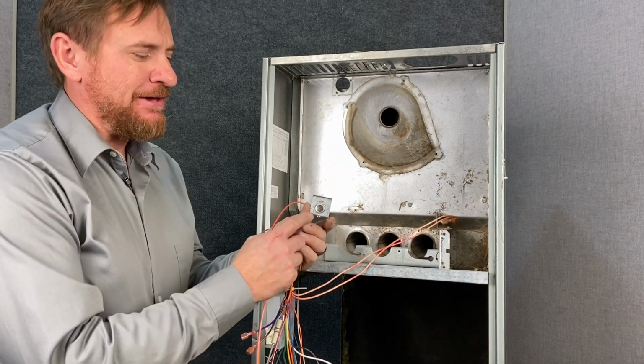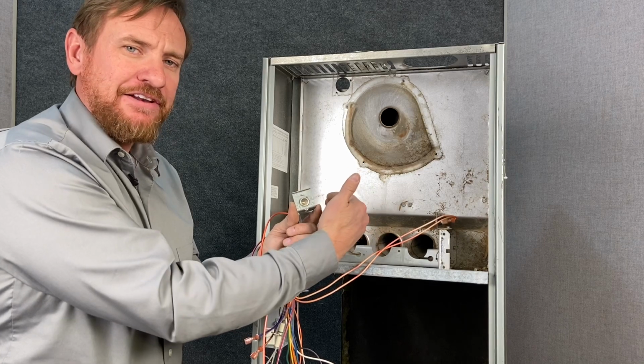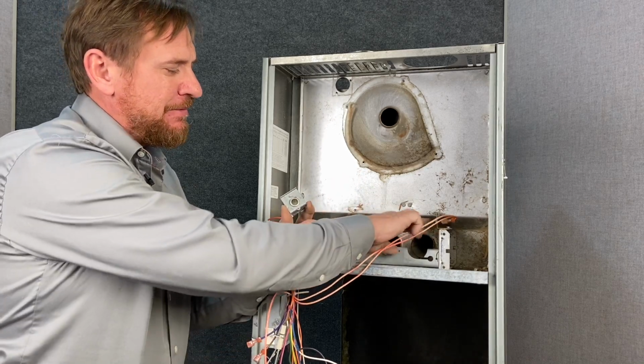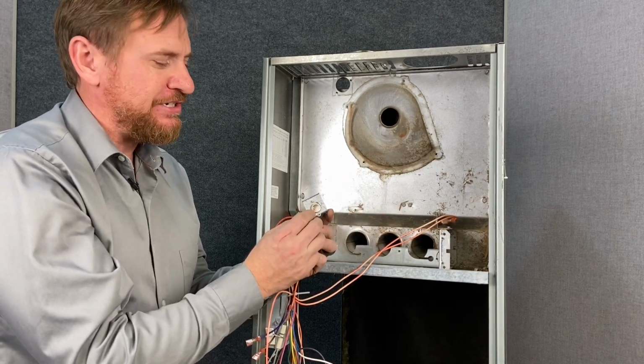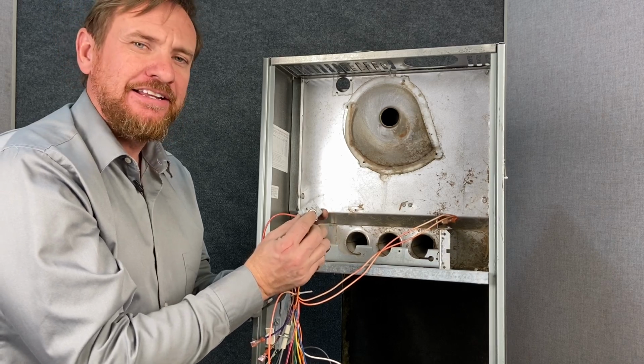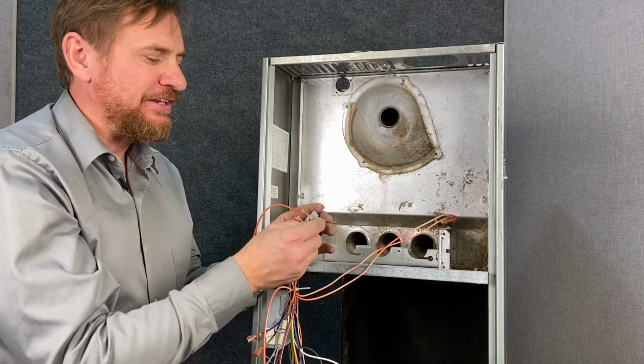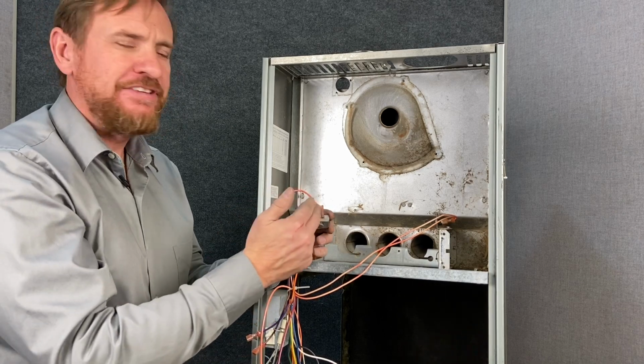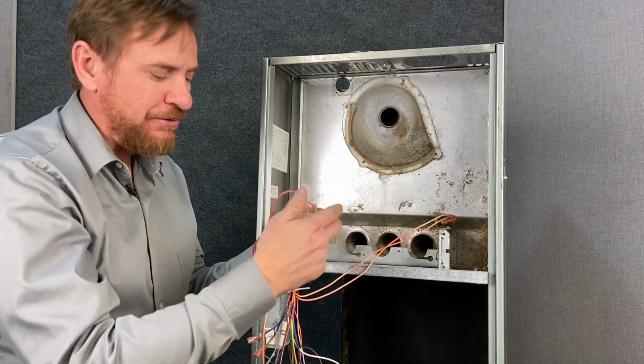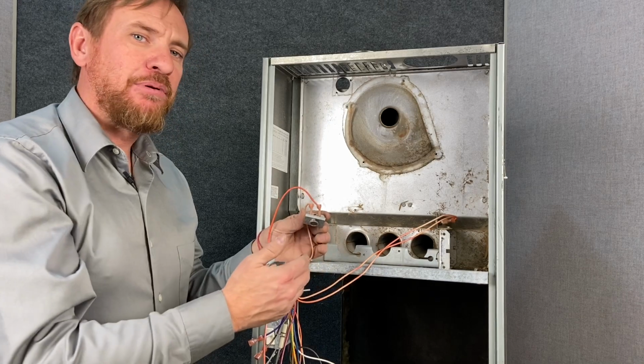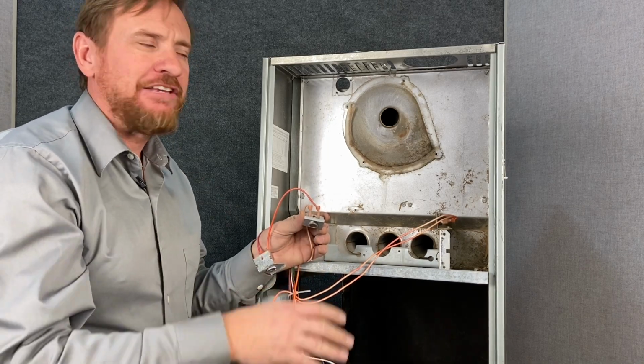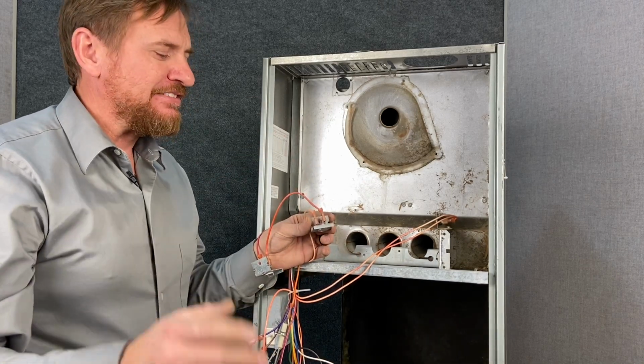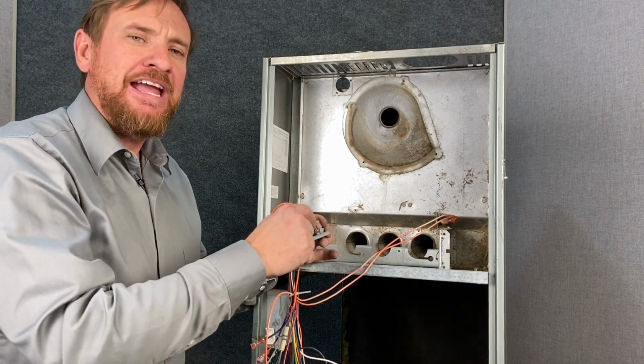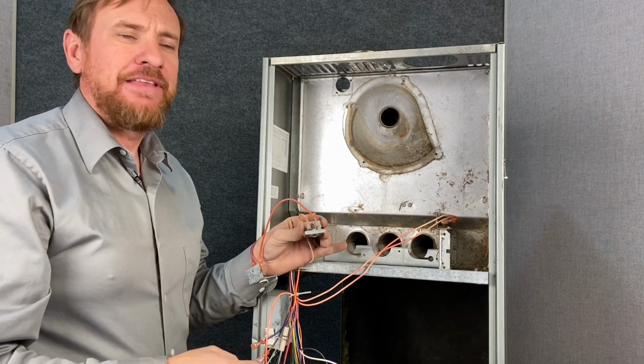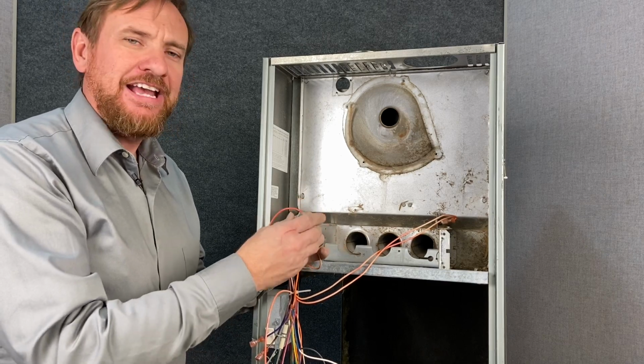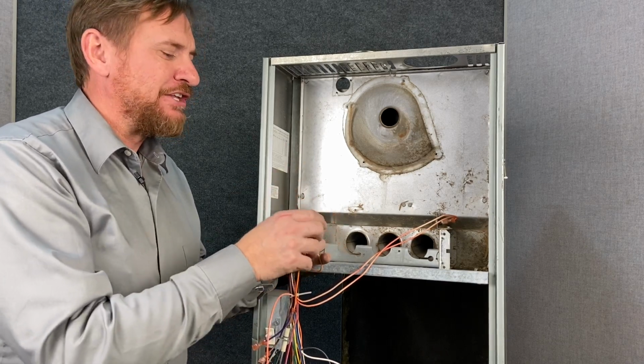Now this is just bimetal, so when the flame was to roll out of the heat exchanger, that flame would come up next to one of these flame rollout switches, and the flame would cause this bimetal to get hot. And when it gets hot, it makes this little click noise, which pops the reset. It opens these wires. Once these wires are open or broken, the IFC knows, hey, we have a problem, and it shuts down the combination gas valves. It shuts down the entire system. Now, as a technician, you have to come out and you have to manually reset that limit switch, the flame rollout, so that it resets.